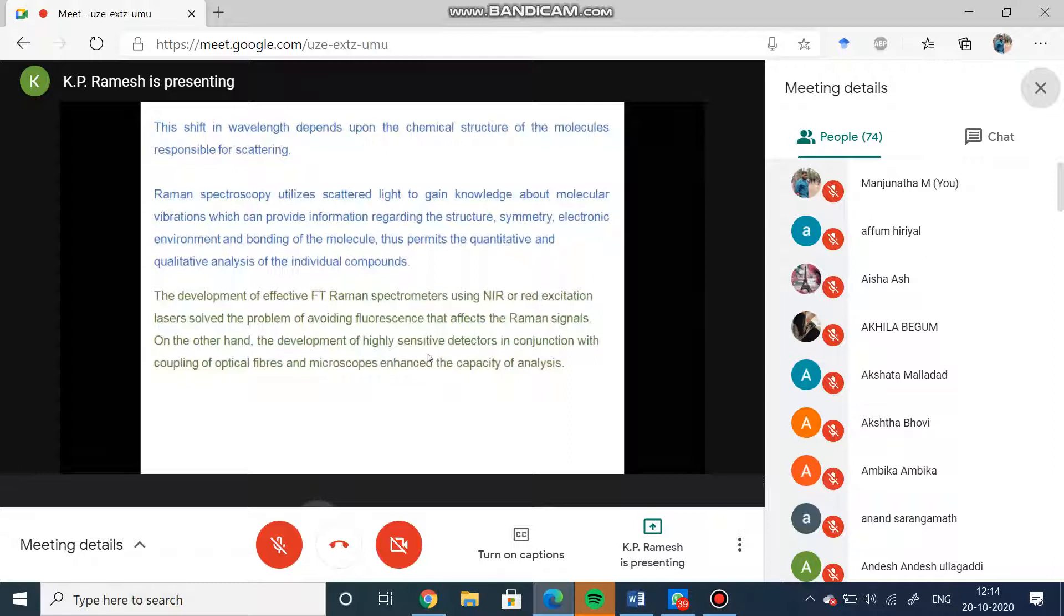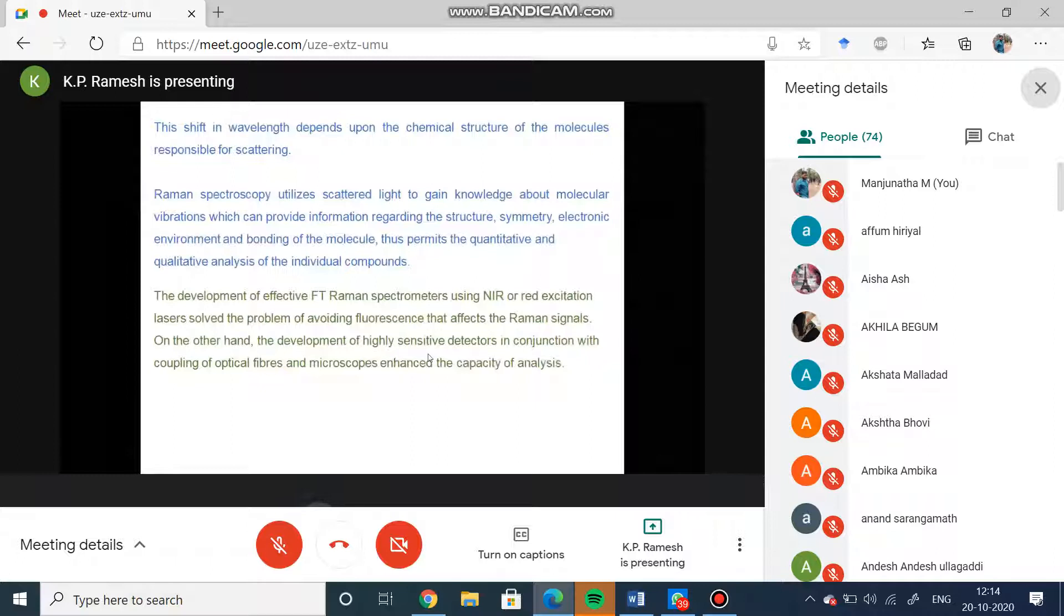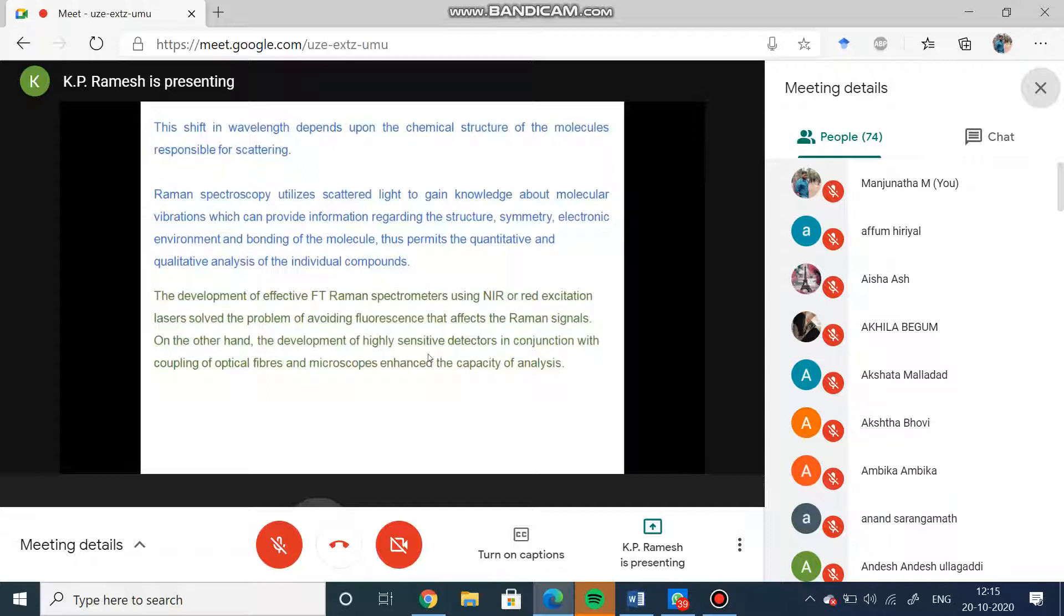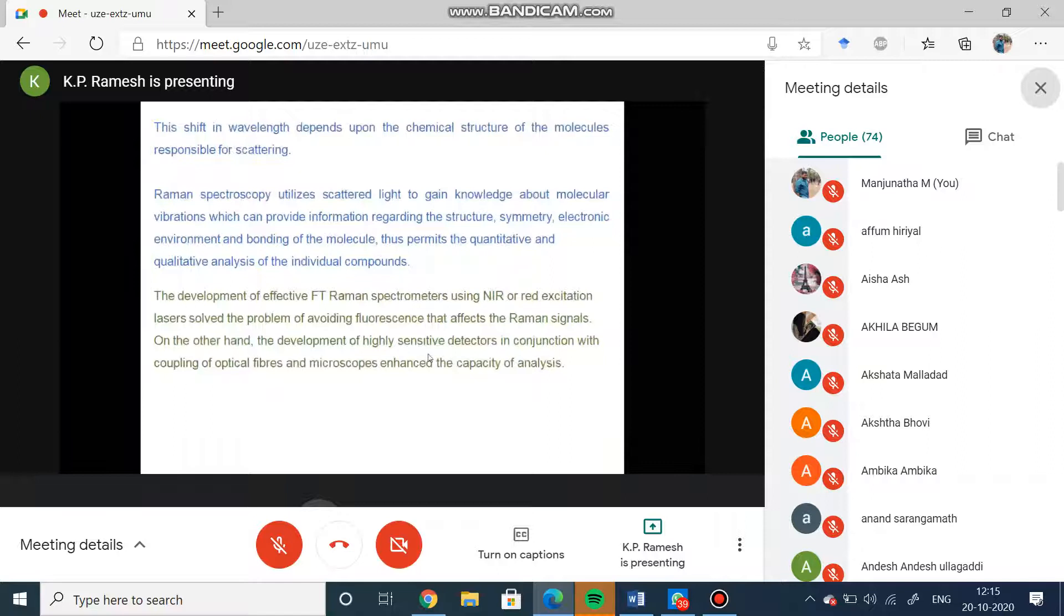The development of FT Raman spectrometers using NIR and red excitation lasers solved the problem of fluorescence, which was a very big nuisance in Raman signal analysis. Now you can see that NIR and red excitation lasers have really improved the sensitivity in conjunction with the optical fibers and microscopes, enhancing the capacity of the analysis. I will talk of all these optical fibers and microscopes.